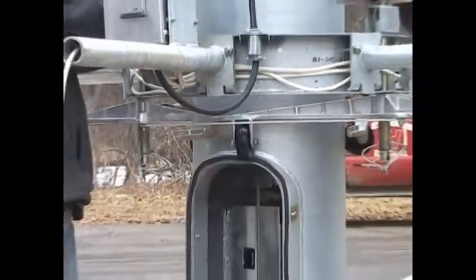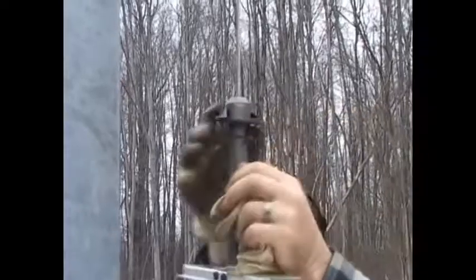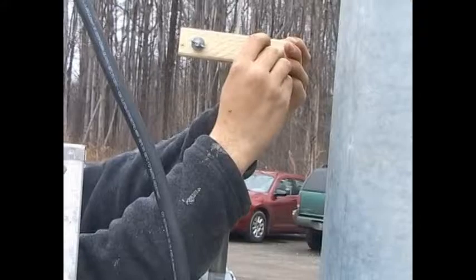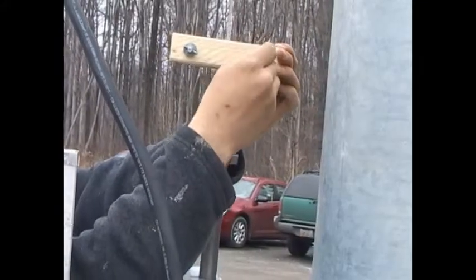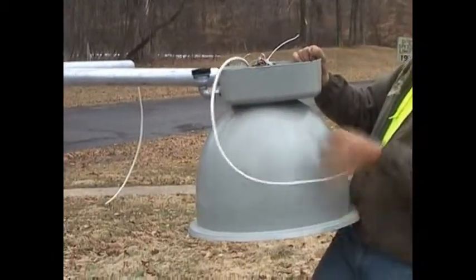Once the ring has been lowered, the split washers can be removed. Latch synchronization blocks should now be installed on the hoisting cables 39 to 41 inches above the top of the pins. The fixtures can now be installed.